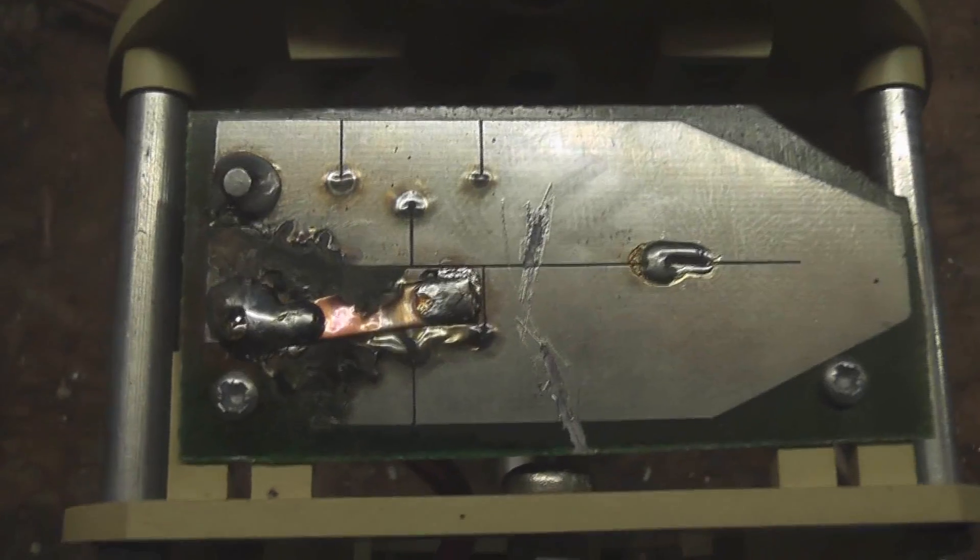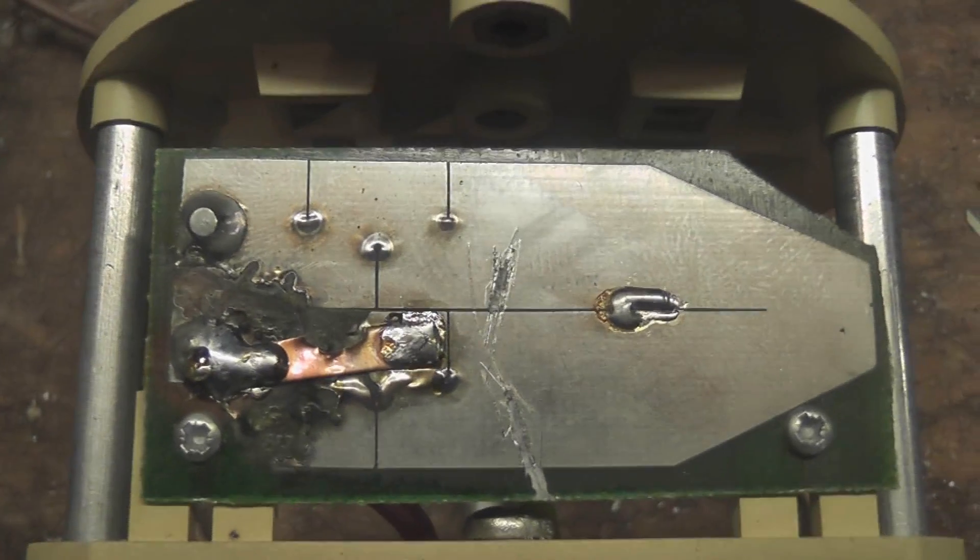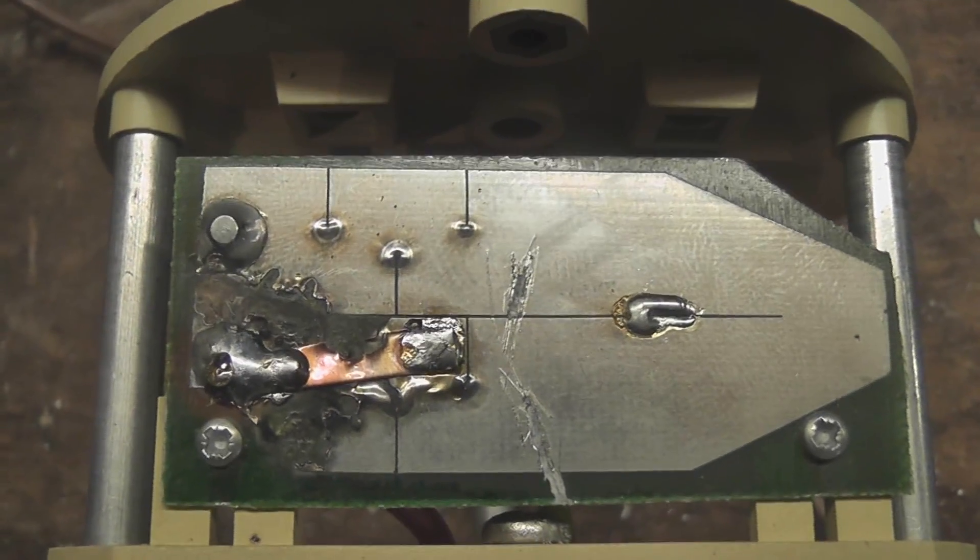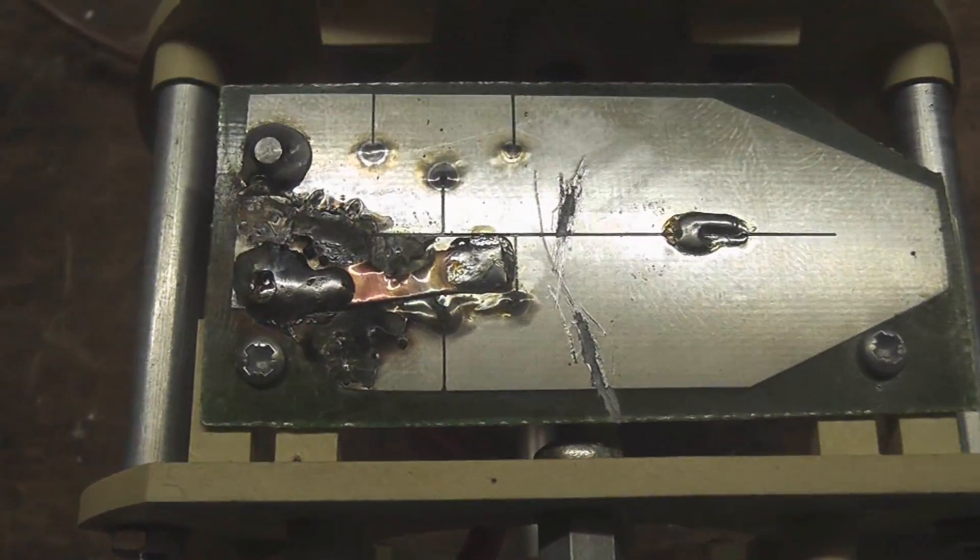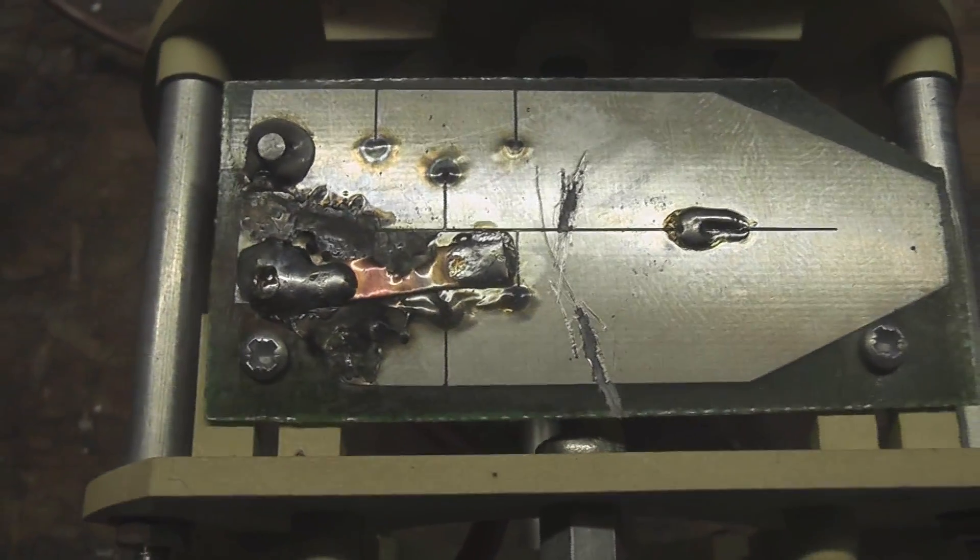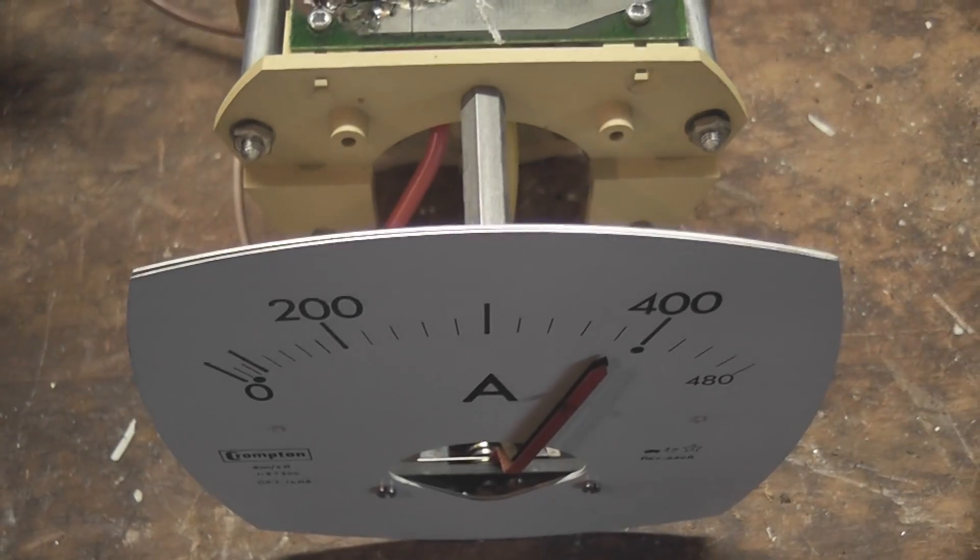As the shunt was destroyed, I have to make some cuts in it to get the calibration right for it. I'll just give it a good long duration test but it sits nearly on four hundred. I may have to make the slot a little bit longer. The thing is that these meters have a thermal lag, these particular type meters.